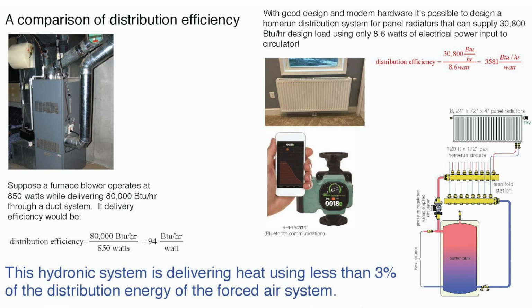And if you do the mathematics of what's necessary for the circulator, that circulator at that point only needs about 8.6 watts to run, to provide the necessary flow to operate that system. And it's delivering a little over 30,000 BTUs per hour. And so the distribution efficiency is almost 3,600 BTUs per hour per watt. So look at the ratio. That hydronic system, compared to that furnace, these are 2 specific cases now, don't generalize it, is delivering heat using less than 3% of the electrical energy that the forced air system required.